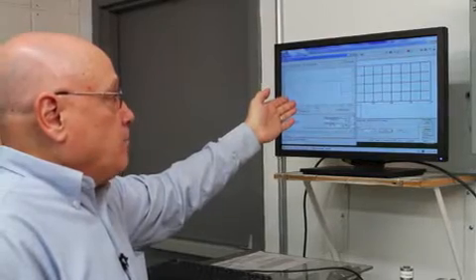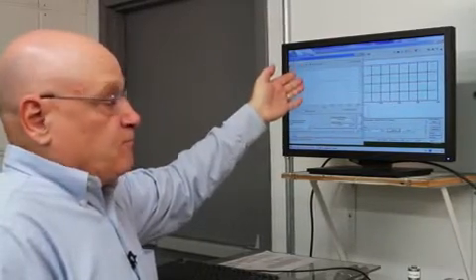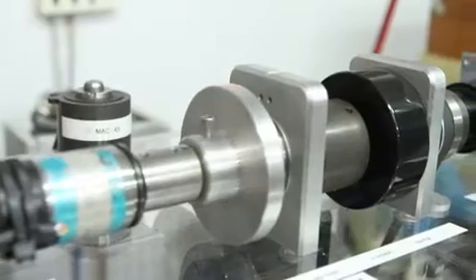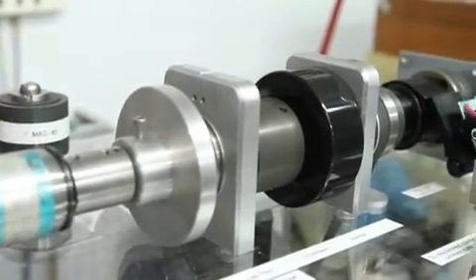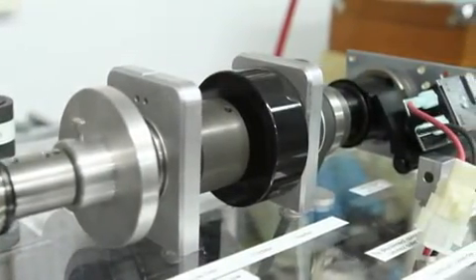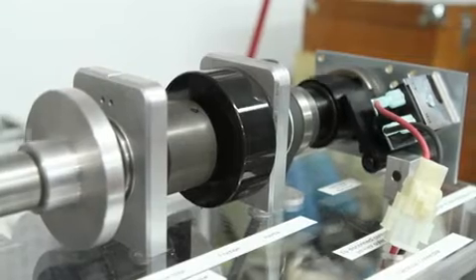The wrap spring can do the same functions as the servo. The wrap spring clutch and brake are designed for lower speeds from 250 pound inches up to over 5,000 pound inches and there's different frame sizes and they have different speed capabilities associated with them.